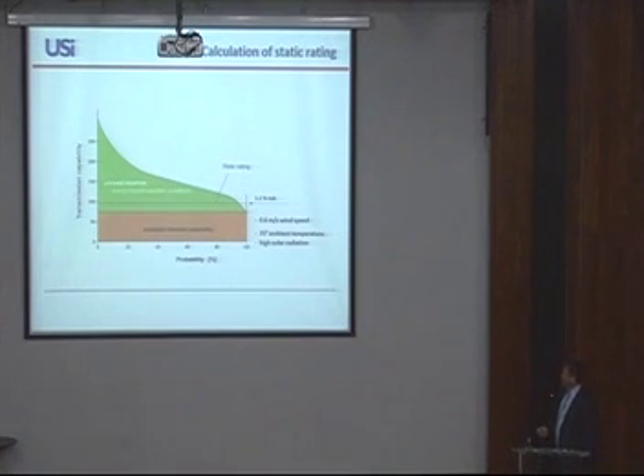Before I come to that: if you are 100% safe, that also means you always have some wind. The temperature is never, or only for a few parts of a year, that high. So the real capacity would not be the static line rating, it would be something higher. All this additional capacity due to more cooling cannot be used. And in order to use a little bit of that, which is what I just explained the designers do today, they assume a small wind speed which cools the conductor. Typically it's 2 feet per second, which is about 0.6 meters per second, perpendicular to the conductor. That results in a higher rating for the operator, so they typically use this value for their operation.